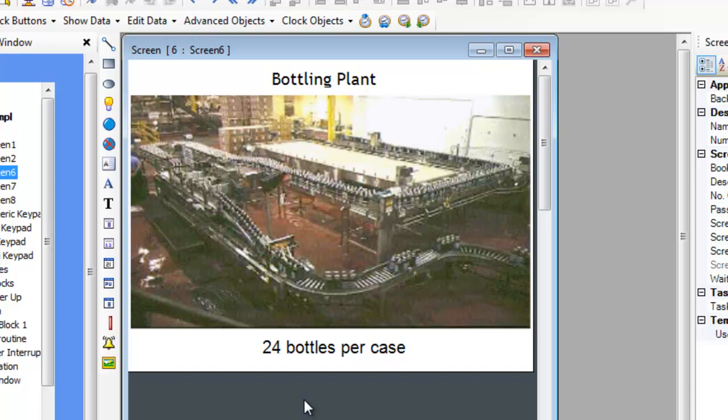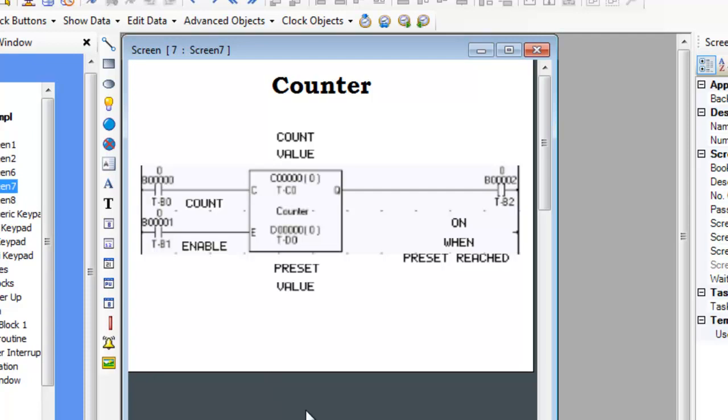The Mapware 7000 software supports two counter functions that can be used in ladder logic. The counter, which increments while the enable input is on, and when the count input contact transitions from the off state to the on state. When the preset count value is reached, the counter stops incrementing and the output turns on. Setting the enable input off resets the counter to 0 and also turns the output off.